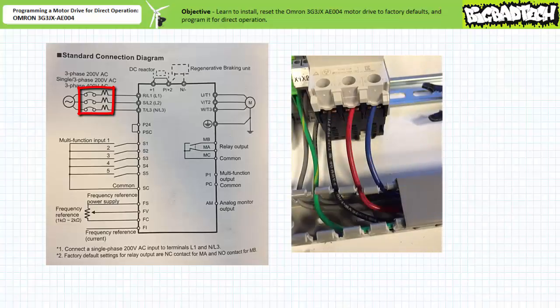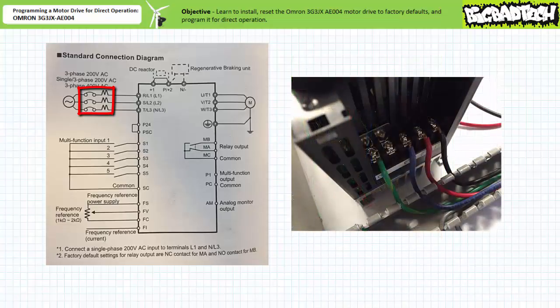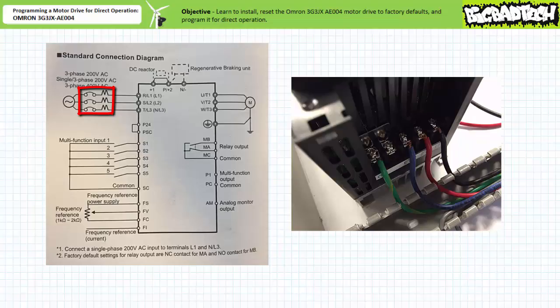The T1, T2, and T3 output of the circuit breaker go into the L1, L2, and L3 primary inputs of the motor drive. The black, red, and blue wires serve this purpose. Additionally, note the motor drive has been grounded using the green wire.